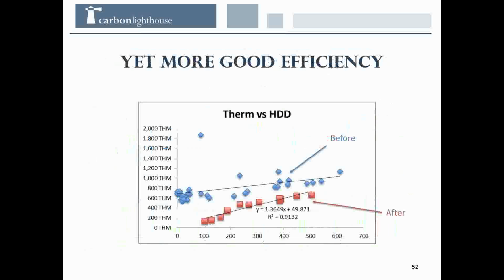If you're doing a gas-only project, there are other ways to verify it. You only have monthly data, so you can't be quite as precise. Basically the blue line is the energy use corrected for temperature before the project was done, and the red line is the energy use corrected for temperature after the project was done. HDD is a heating degree day, by the way, a measure of temperature. The important thing is that when you compare utility use ahead of time and after, it should actually be lower, and that difference should match predictions.